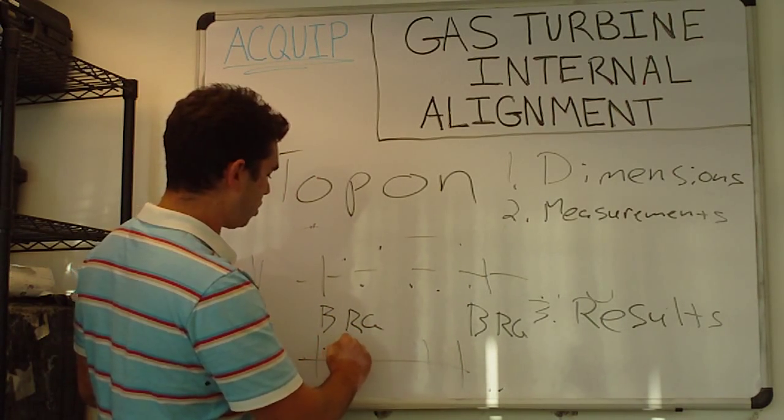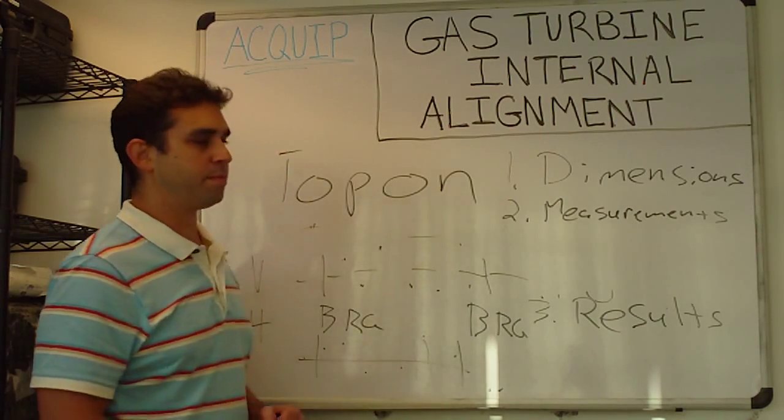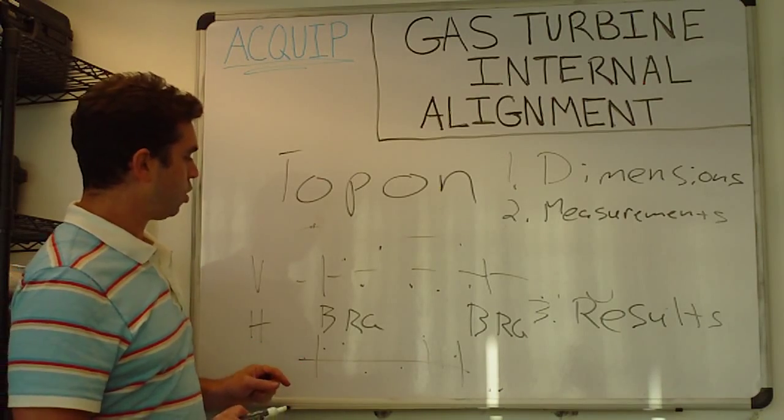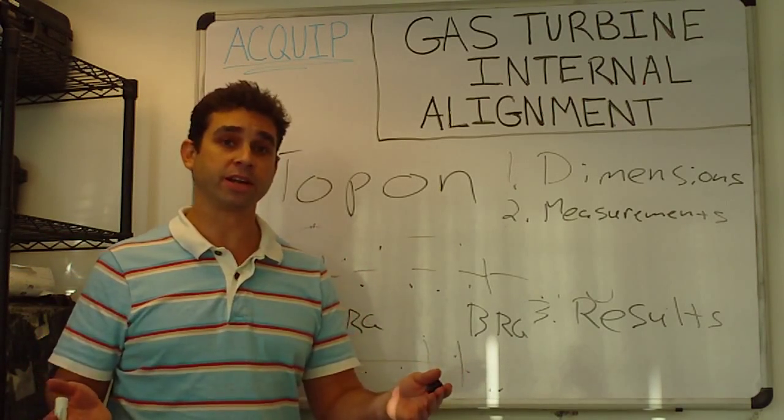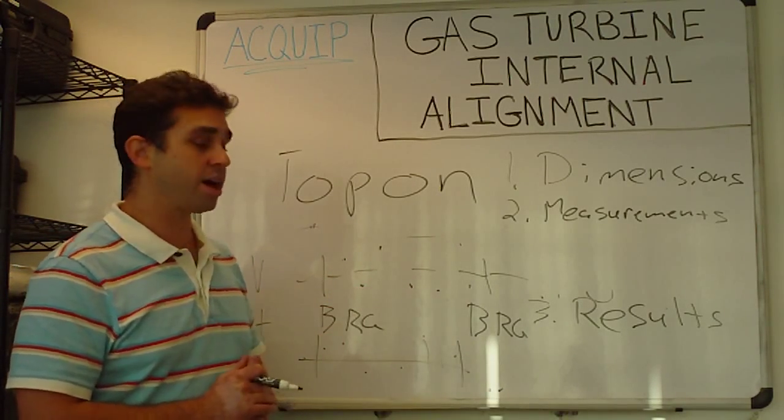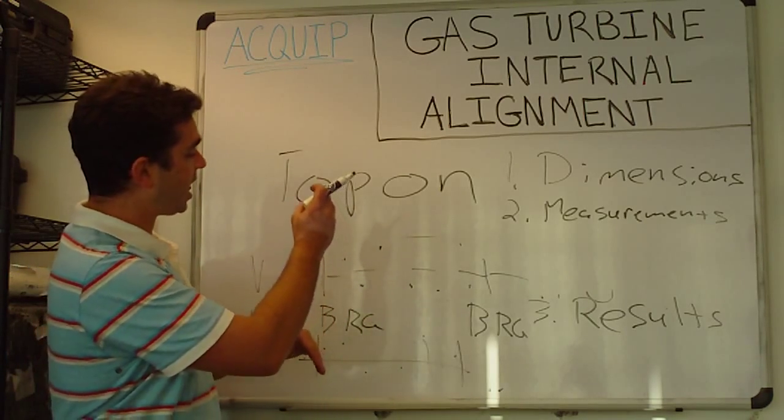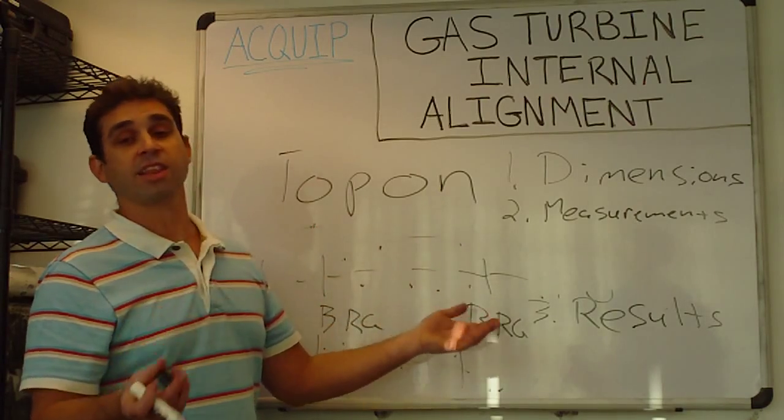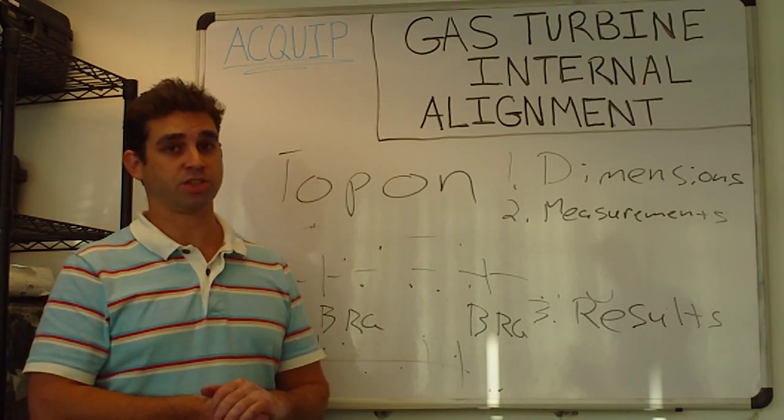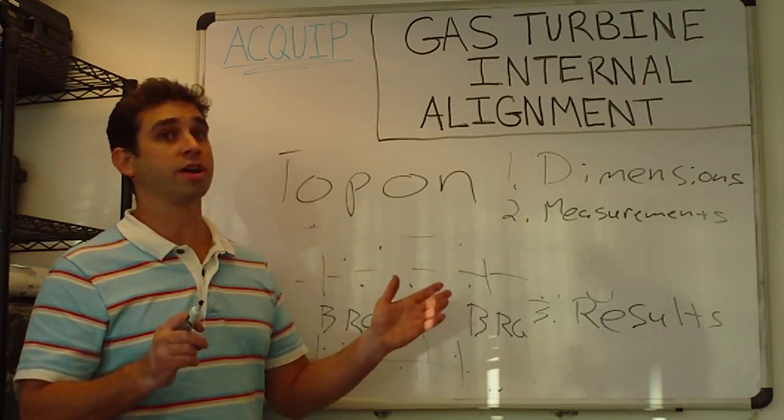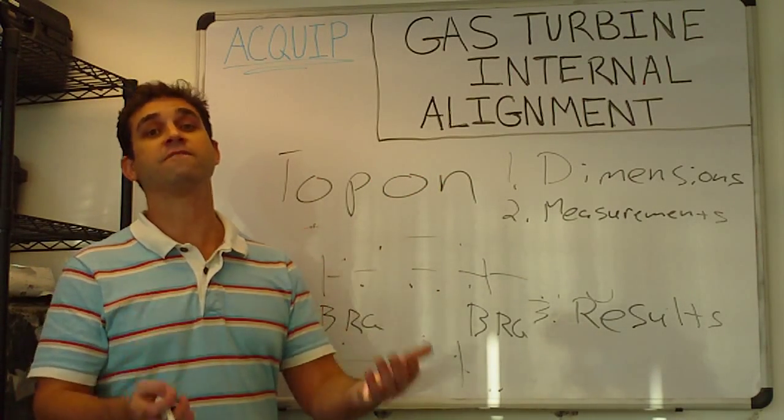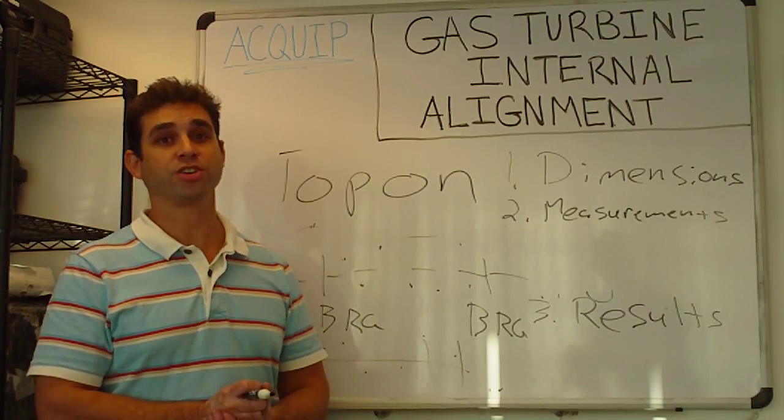And then we can make our alignment moves based on this set point, whether it be moving a bearing or moving one of the other internal components by sliding them on each other. There's a lot that goes into doing this gas turbine internal alignment, but as long as you follow these steps, you're going to be able to do a very good internal alignment on your gas turbine.